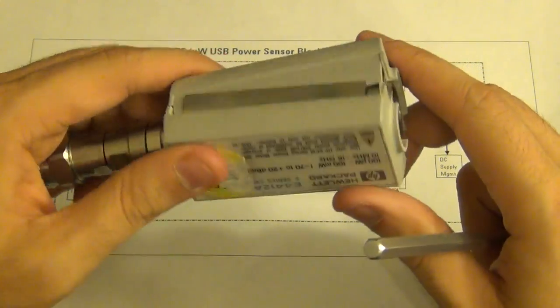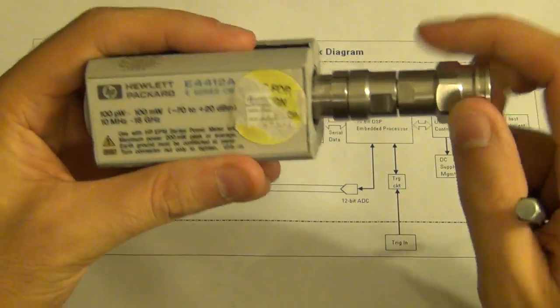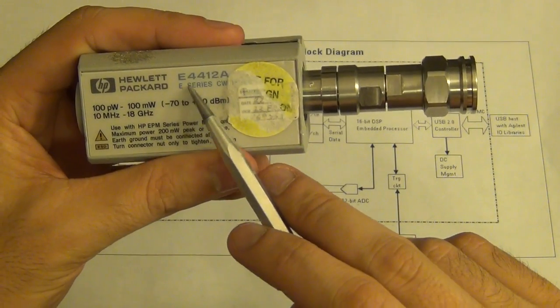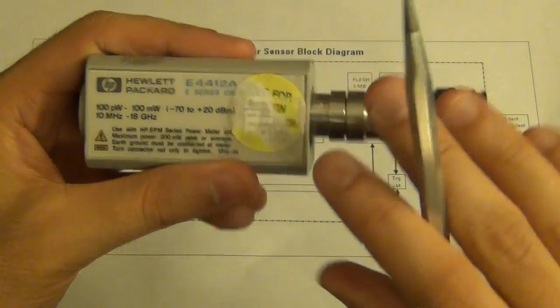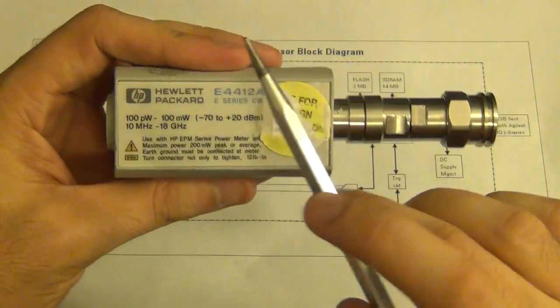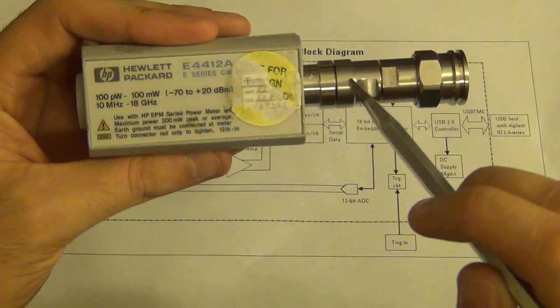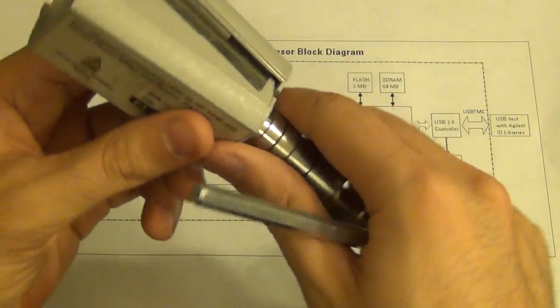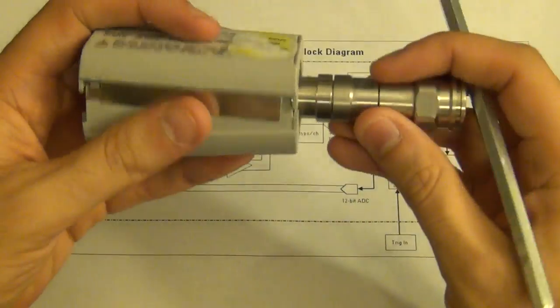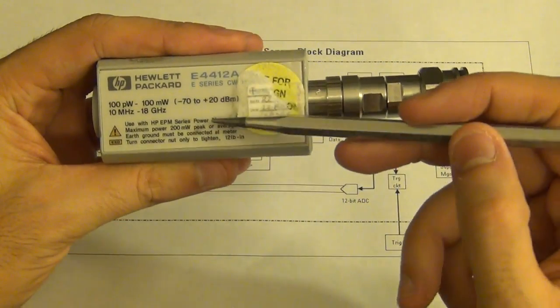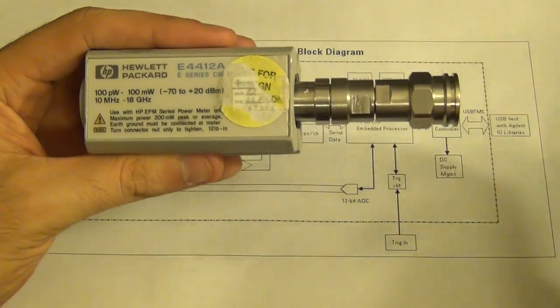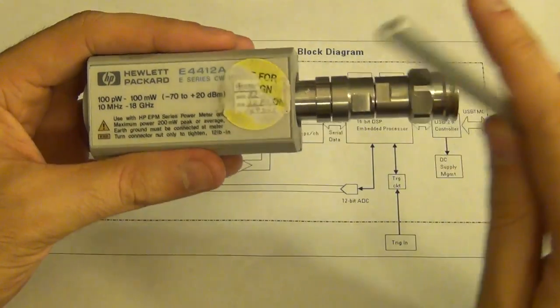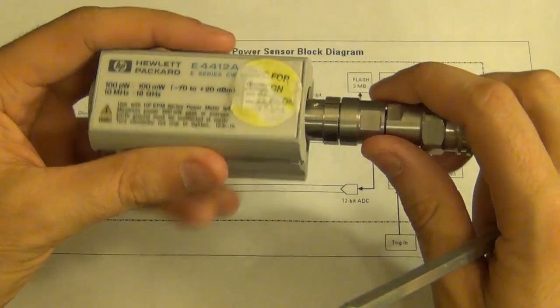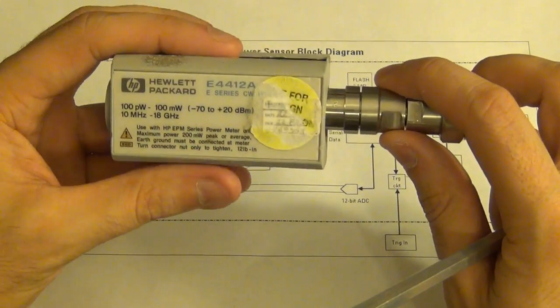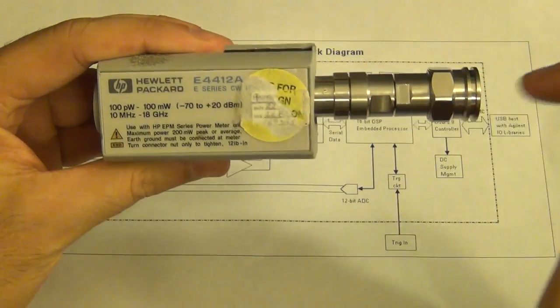This one I took the casing off because I was curious to see what's going on here. This was the E-series that I was talking about. As soon as you plug these E-series in there, the calibration coefficient gets sent onto the power sensor and then the power meter, and it gets automatically calibrated, so you don't need to worry about the table. I found this actually in the garbage because it was completely dead, so I picked it up simply because of my curiosity.